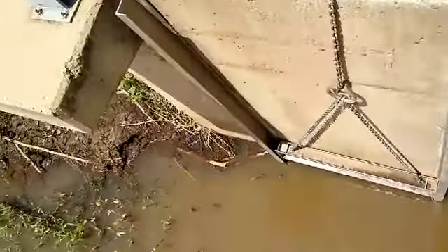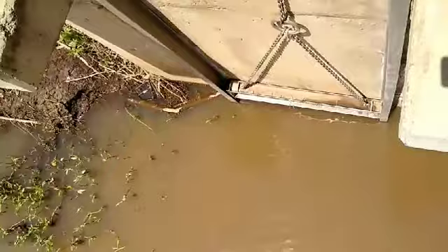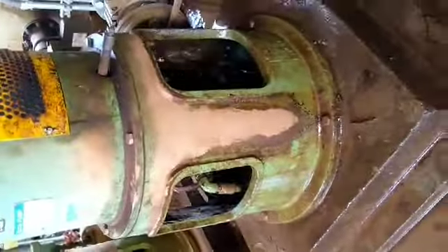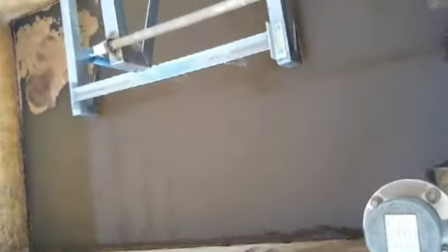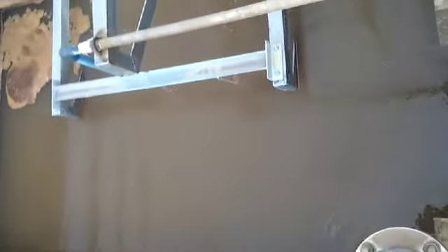At the intake, water from the river is diverted so that it can go through the screening processes. Screens are structures that are used to remove large floating objects such as leaves, twigs, rocks and other debris from water. After screening, water is pumped at 2.6 meters cubed per minute to the receiving well, which is about 2 kilometers from the intake. What's a receiving well? This is a structure that is used to receive water that is pumped from the intake, I mean raw water.